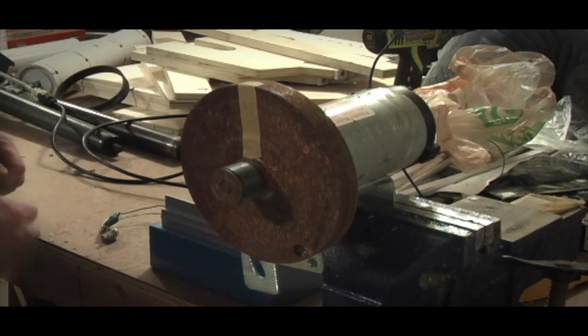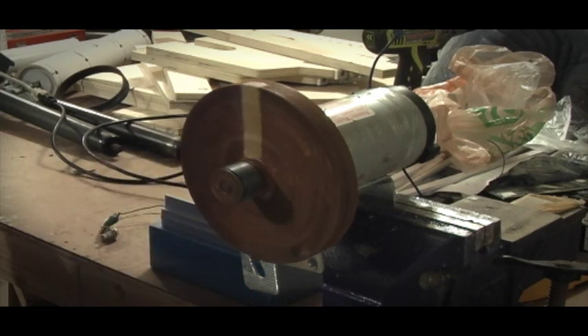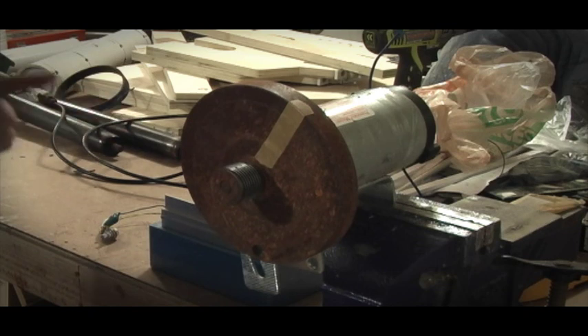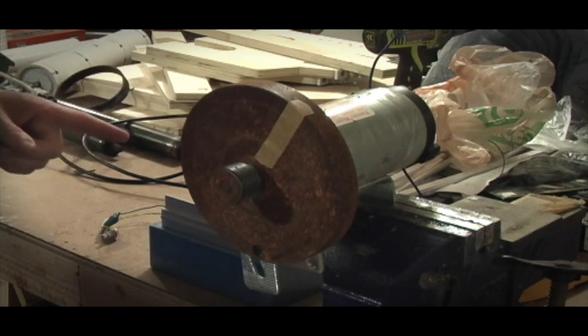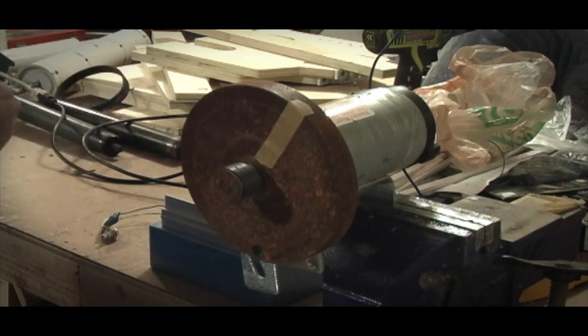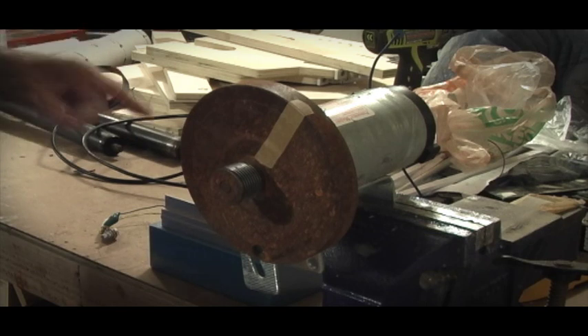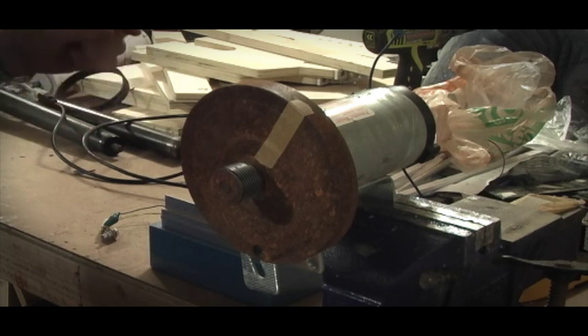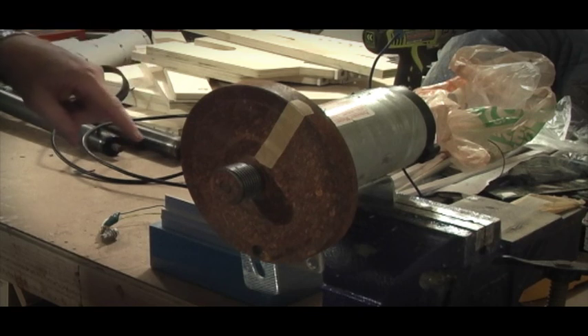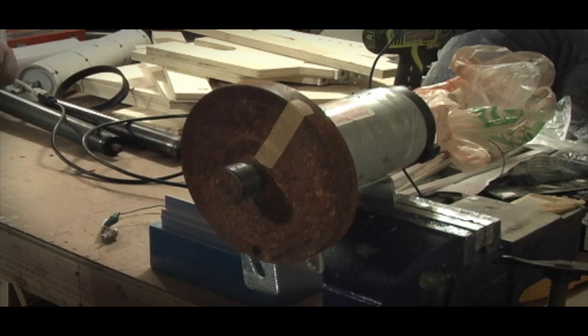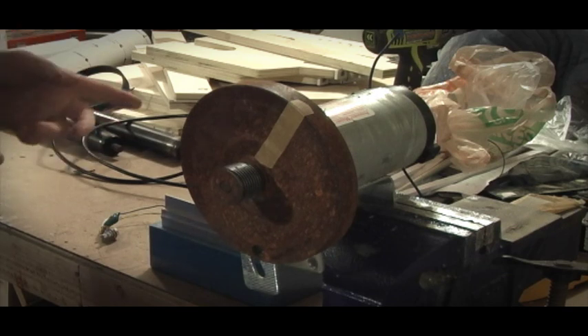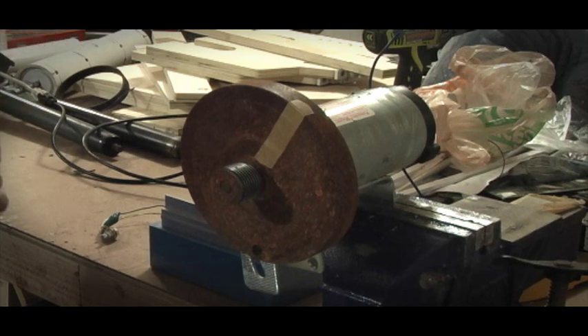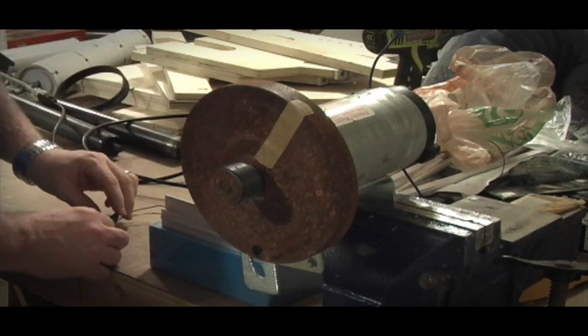All right, so we are wired up. We are ready to go. Right now, with the pot turned all the way down, I don't have any LEDs showing on the controller, which as I understand it tells me there is no speed control present, there's no DC voltage being received by the controller, and the SCRs are not switching. As soon as I apply the voltage to those terminals, you won't see them, but they will come on.